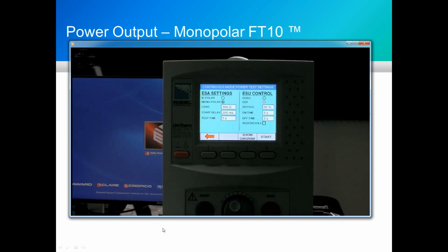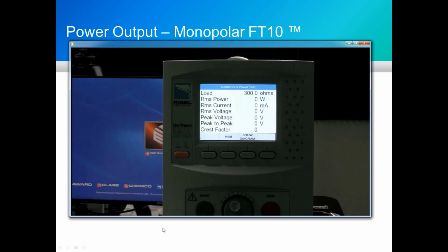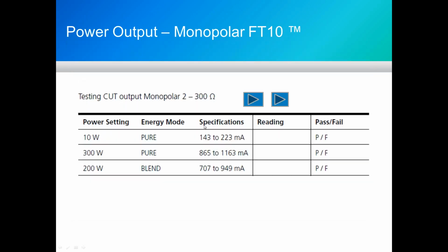My connection diagram. All of the data that you see here is the data that would be captured in the internal memory of the Unitherm when we're doing a test sequence in auto mode. And as you see, we were within the specification of acceptance for current.